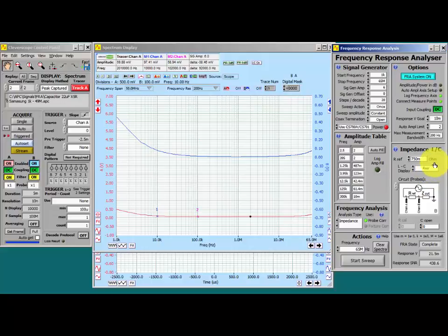We're using a very low impedance reference, 750 milliohms, because we are going to be trying to measure down to a few milliohms. We're going to use circuit B in which the unit under test is directly probed with channel B.